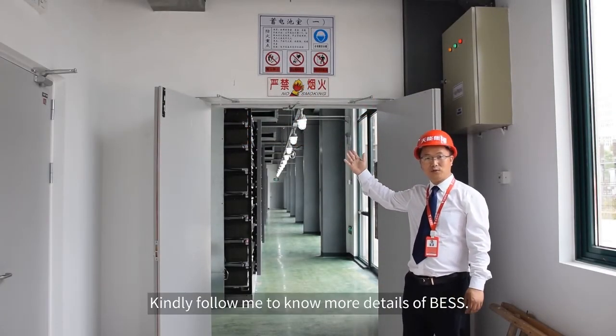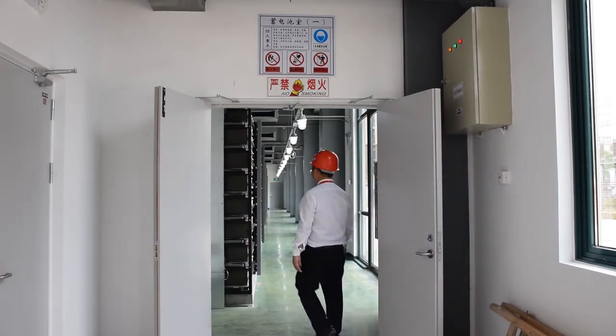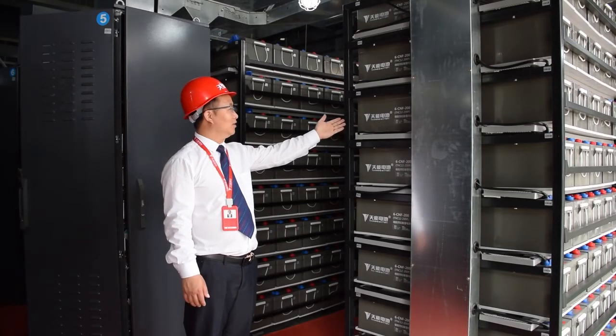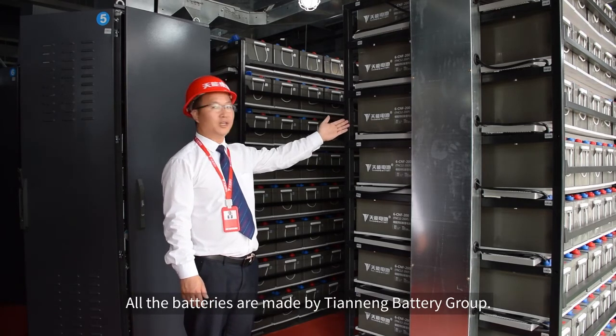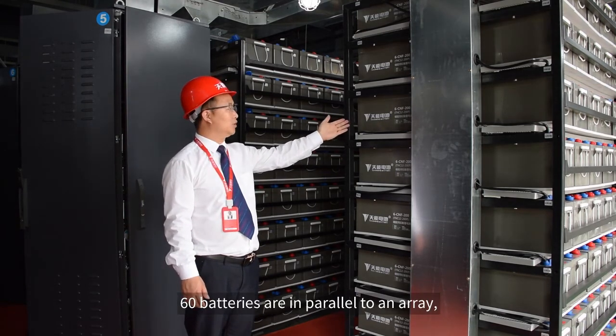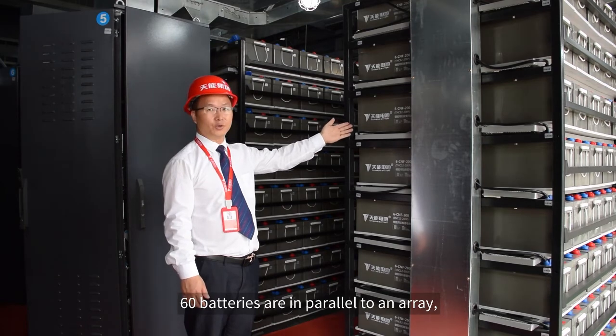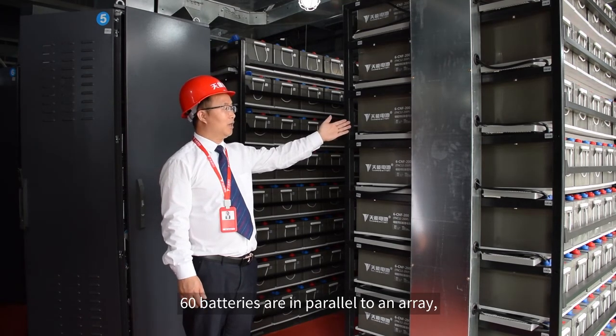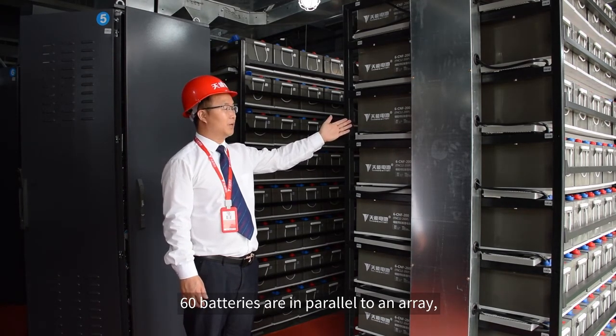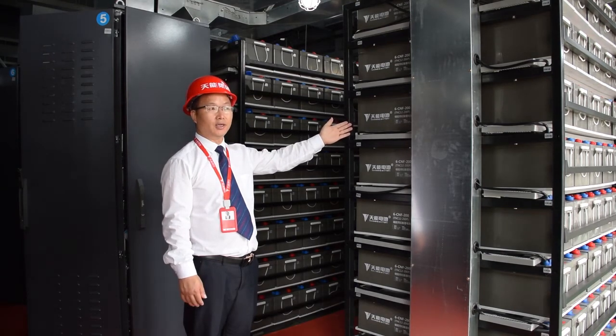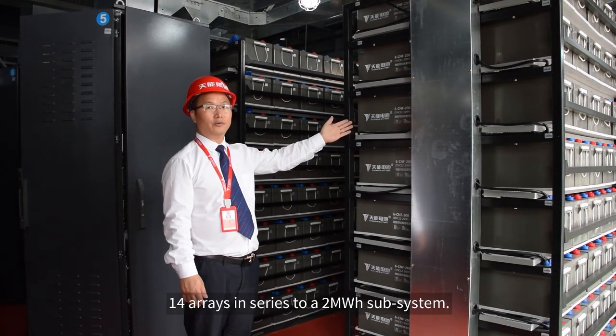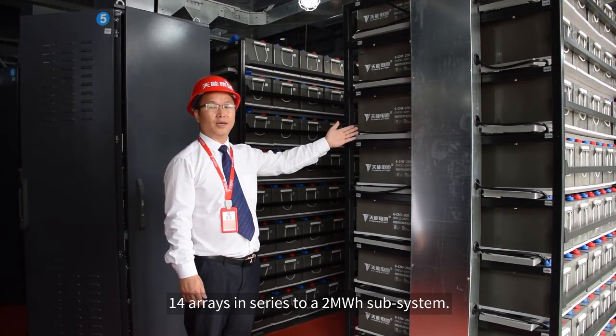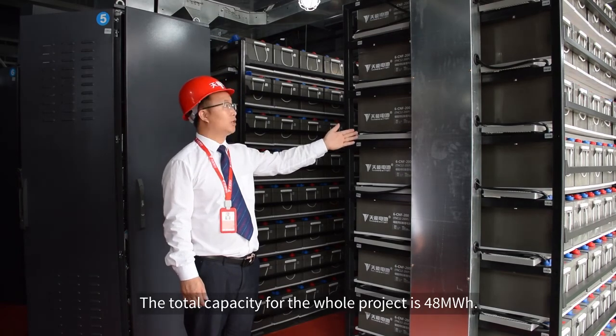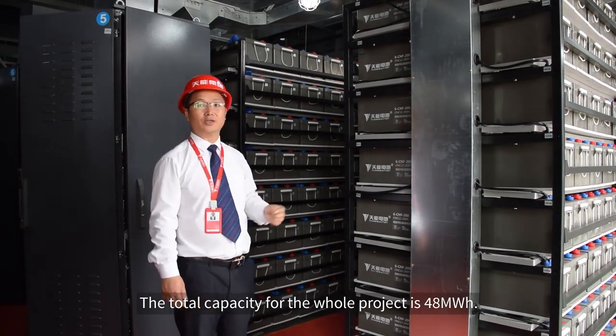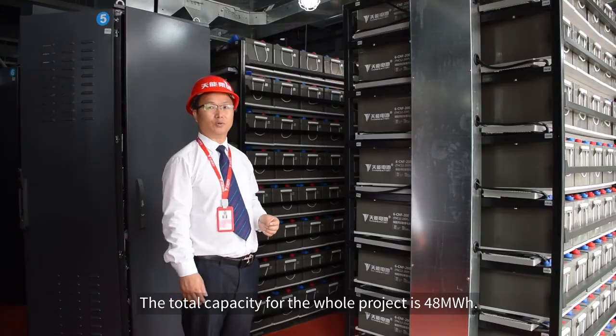Follow me, let's go have a look. All these batteries are made by Tianneng Battery Group. This battery is a lead carbon battery. They have 60 batteries parallelized into an array, with 14 arrays in series to each other, making a 2 megawatt hour subsystem. The total capacity for this whole project is 48 megawatt hour.